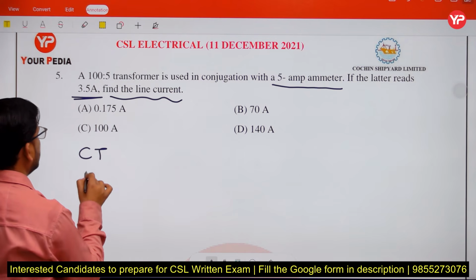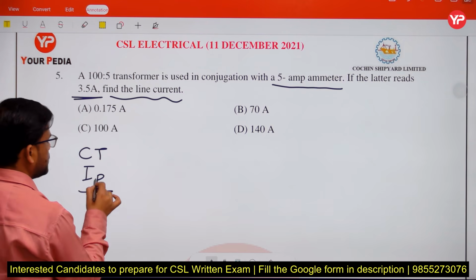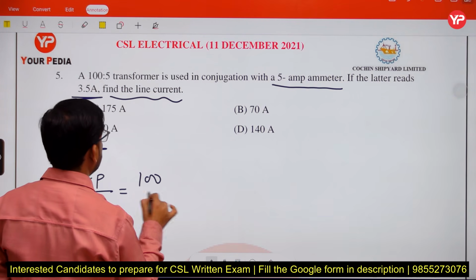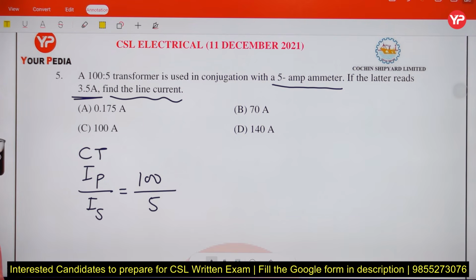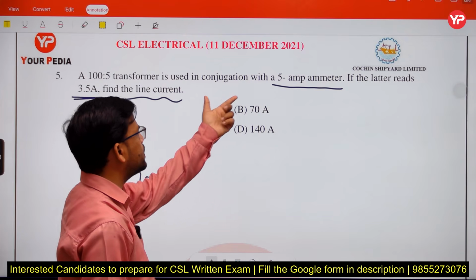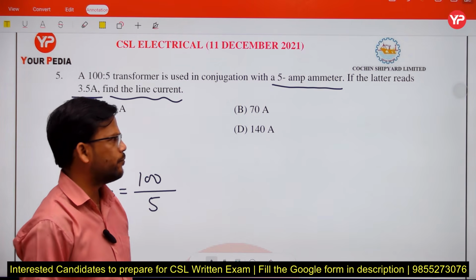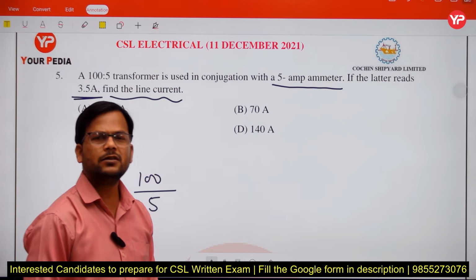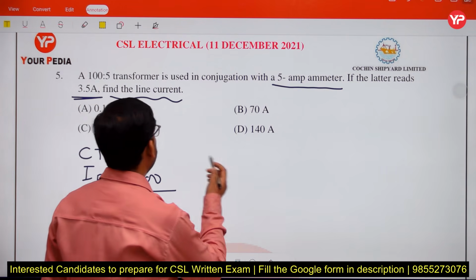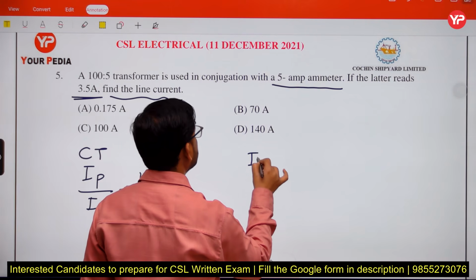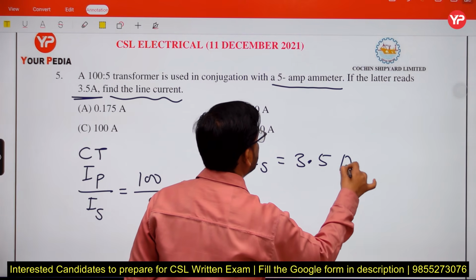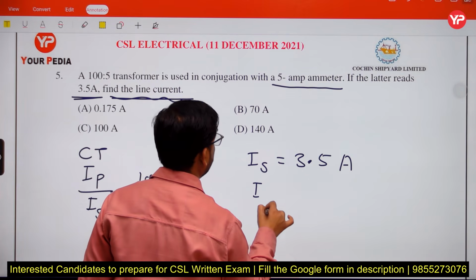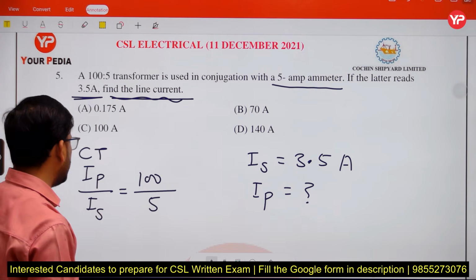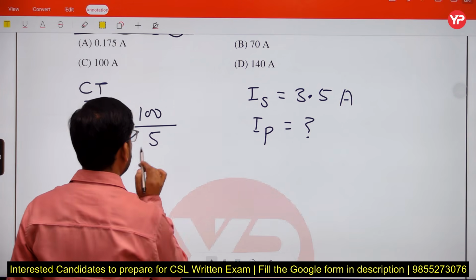This is a current transformer, and the ratio of current IP upon IS, that is primary current upon secondary current, is 100:5. This transformer is connected in conjunction with a 5 ampere ammeter, which reads the current on the secondary side, and that value is 3.5 ampere. The question asks for the line current, that means the primary current. We know the ratio of IP and IS is 100 upon 5.